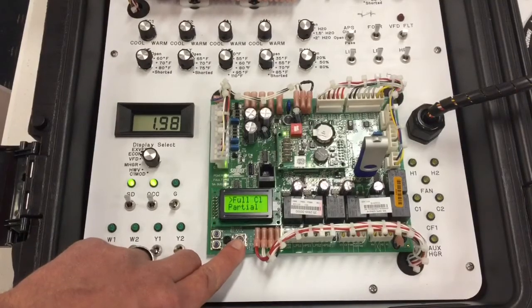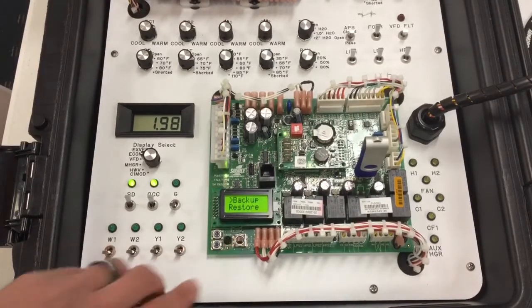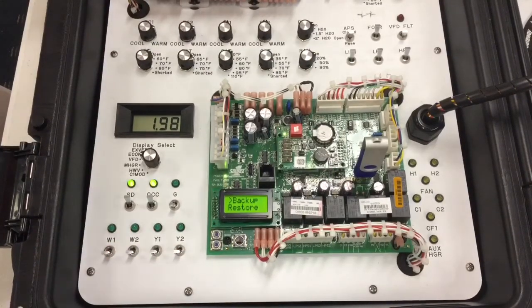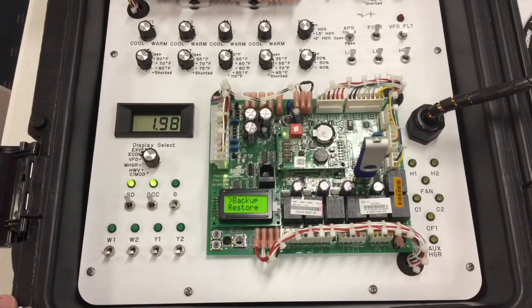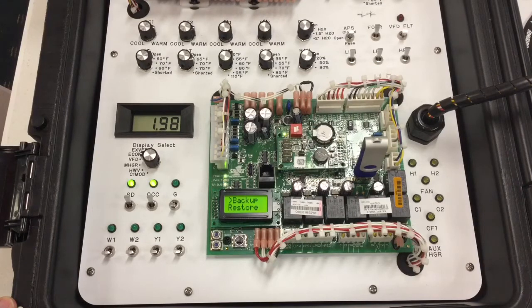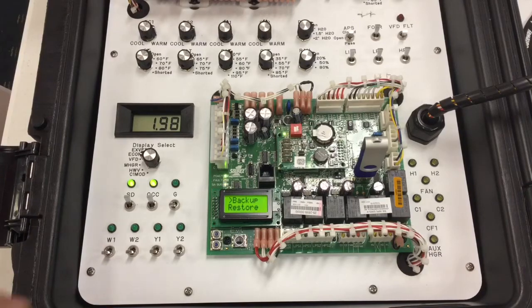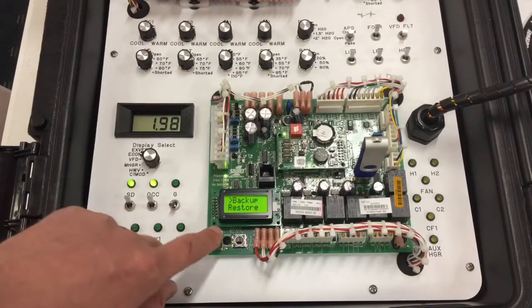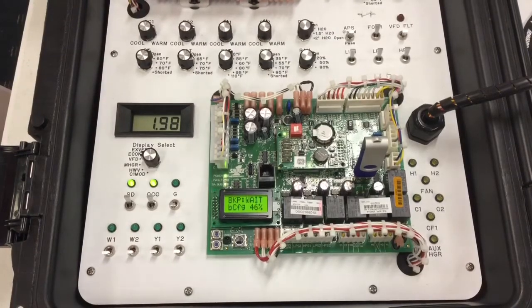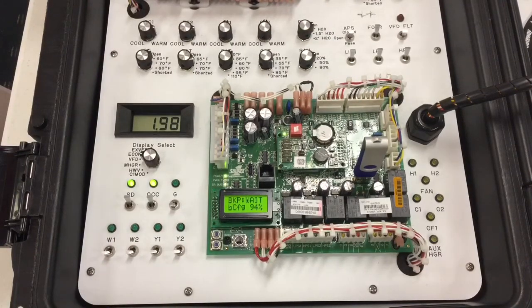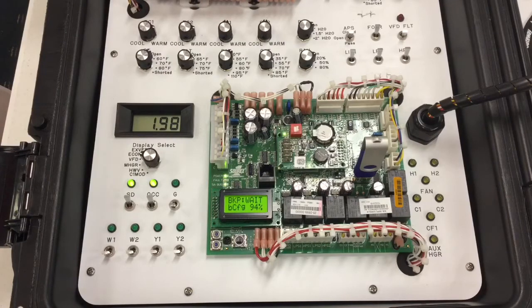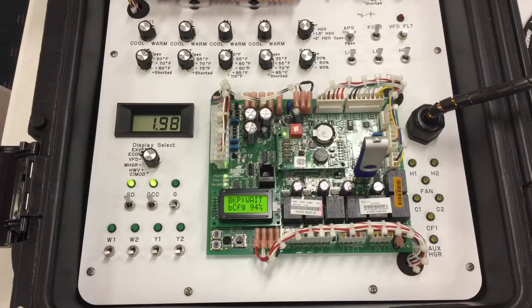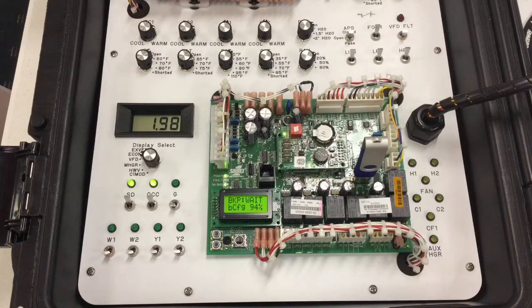A backup would be performed if a system control board determined it needed to be replaced. So if you had called into technical support and we determined that the control board was bad, we would ask you to do a backup of the system before replacing the control board. When your cursor is next to backup, press the enter button one time. At this point, you'll see a backup wait and an estimated time of completion. This usually doesn't take very long. Wait until the screen says backup OK or backup complete.